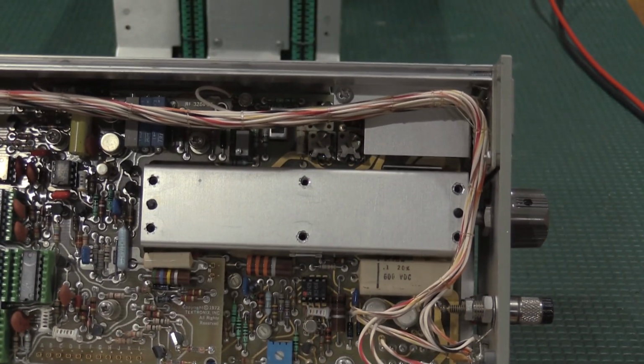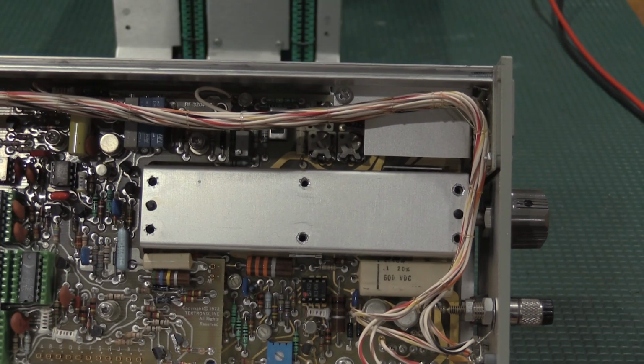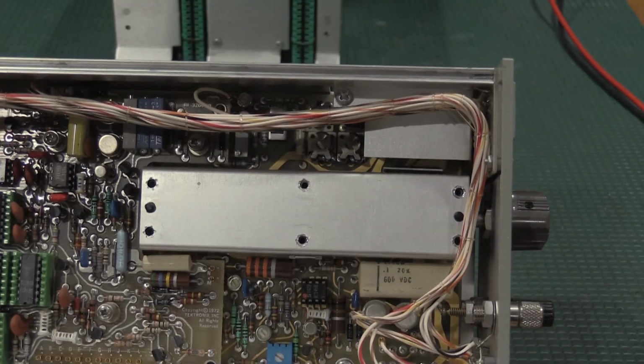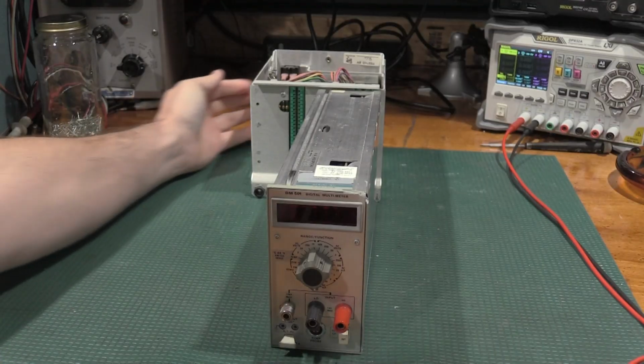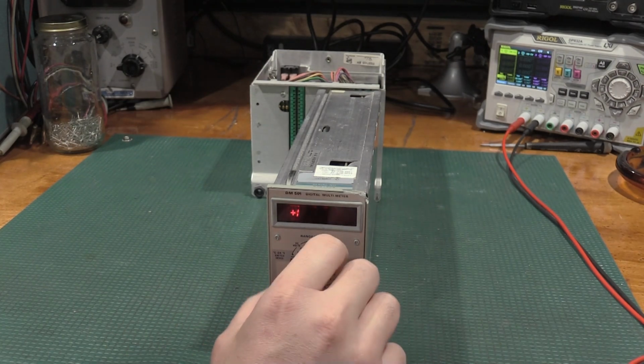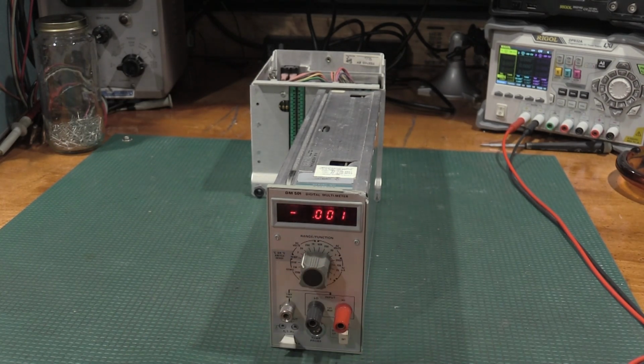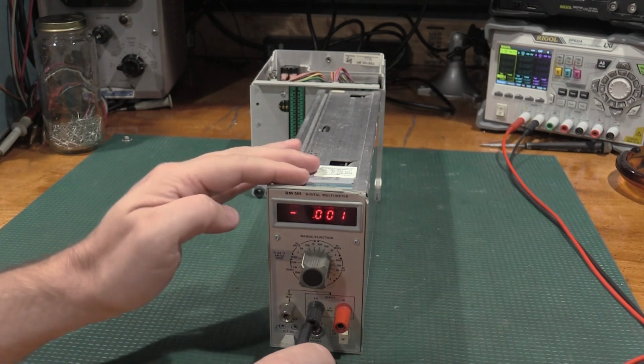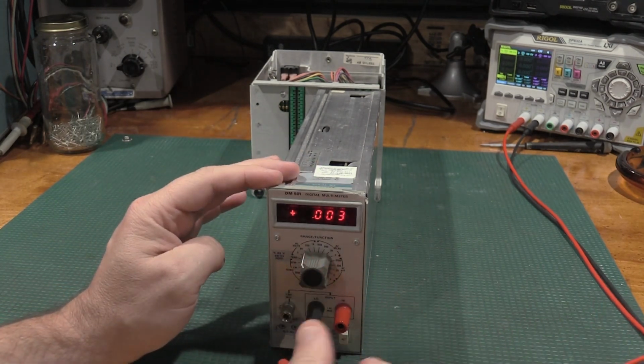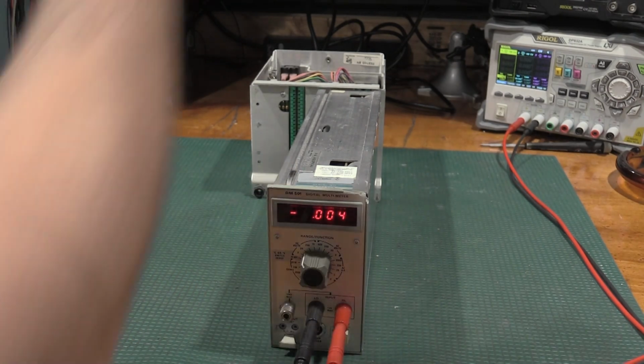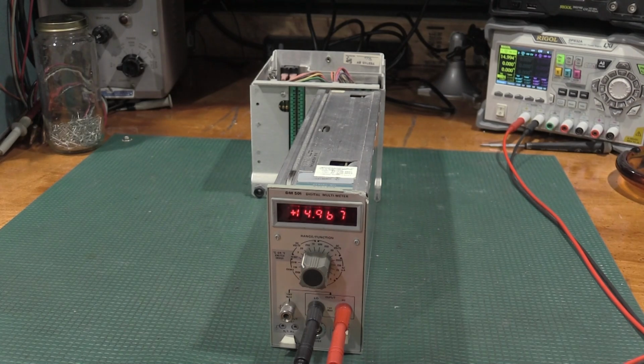And then we'll end up letting this warm up. So I'll get the screws zapped in, and then we'll fire it up. Okay, there shouldn't be any magic smoke problems with this one. Oh, that's acting a lot better, actually. Alrighty. Let's go ahead and hook up our 15 volts again. And we didn't even change the alignment on it, so that looks very healthy. So we're going to let that run, let that sit. We'll fire up the standards here in a little bit and just kind of spot check it.